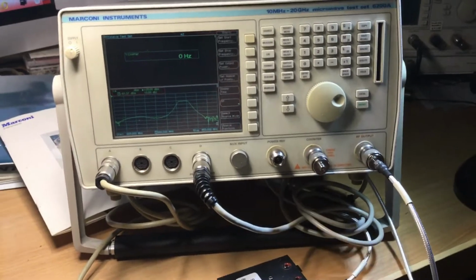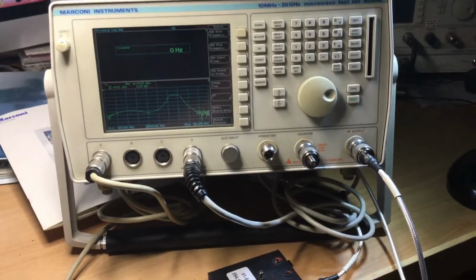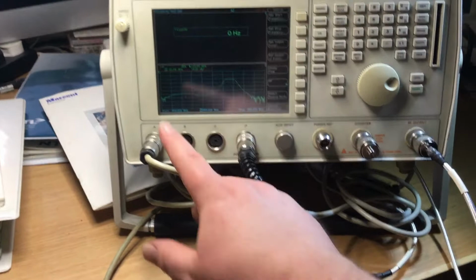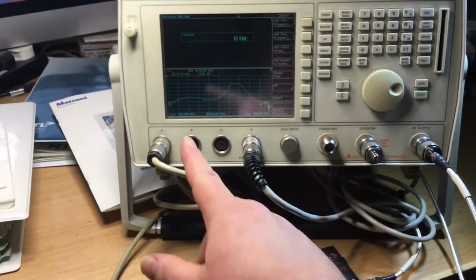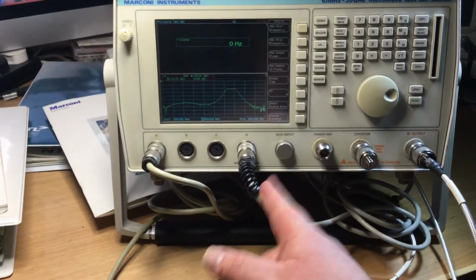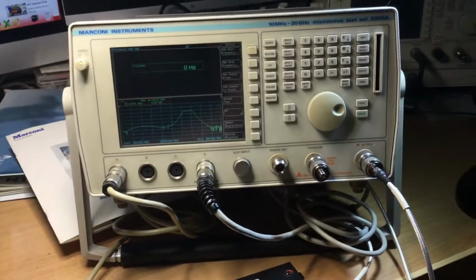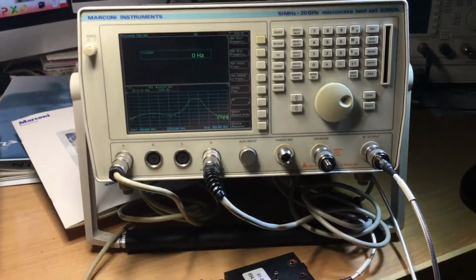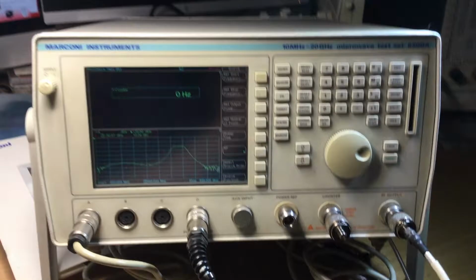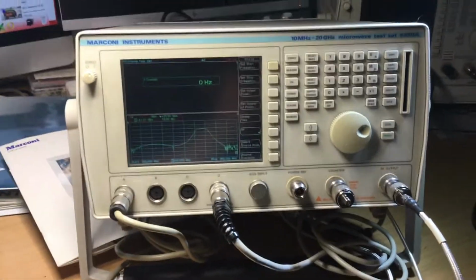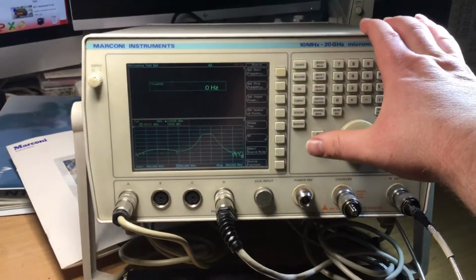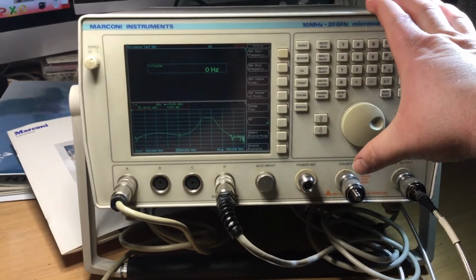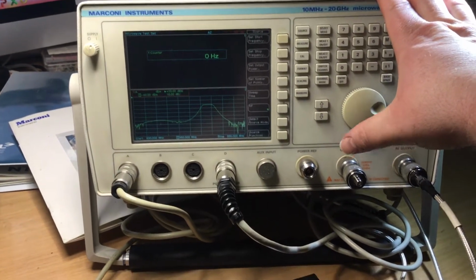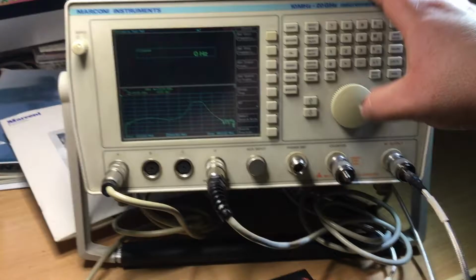You've got to be really careful with these test sets, because the power sensors that plug into these ports - the scalar sensor and the RF power sensor - aren't like what's on a traditional radio test set where you can transmit lots of RF power into it. You can burn them out very easily, so you've got to be so careful when making measurements.